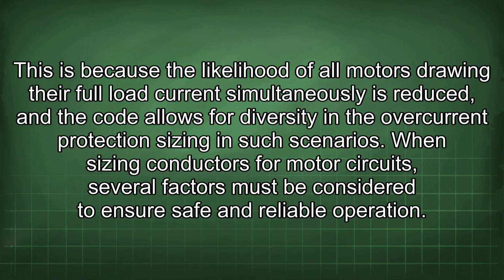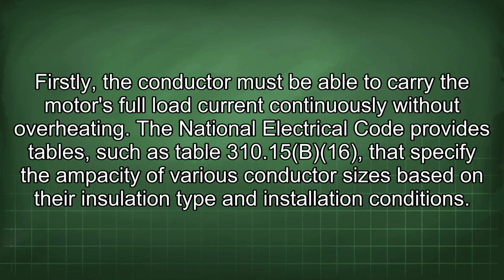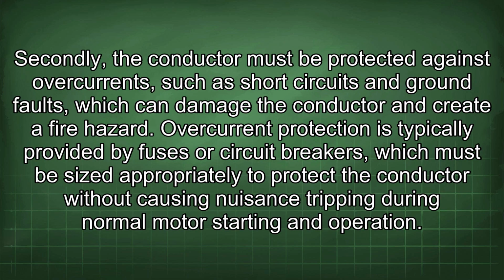When sizing conductors for motor circuits, several factors must be considered to ensure safe and reliable operation. Firstly, the conductor must be able to carry the motor's full load current continuously without overheating. The National Electrical Code provides tables, such as Table 310.15(B)(16), that specify the ampacity of various conductor sizes based on their insulation type and installation conditions. Secondly, the conductor must be protected against overcurrents, such as short circuits and ground faults, which can damage the conductor and create a fire hazard.